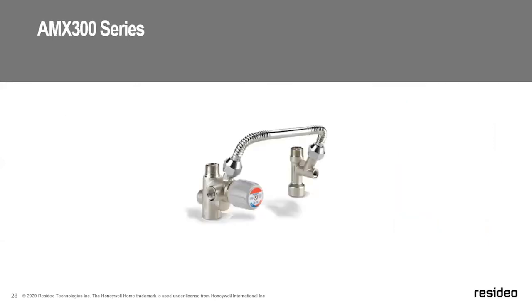We also, on our potable side, so far we've talked about heating. On our potable side, we have mixing valves. Pictured before you is an AMX300 mixing valve. What that would do is thread right on top of a water heater. And you might ask yourself, why would we want a mixing valve on our water heater? And there's a number of reasons.